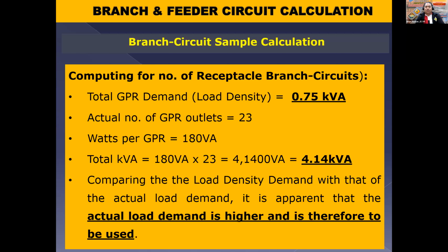Now, whichever is bigger, the load density or the actual load. In this case, mas malaki si actual load. So, which yung gamitin natin? Si 4.14 or the actual load, di ba? So talaga yung mas malaki. So during this stage, mag-validate na tayo, no? I-adjust na natin yung design natin. Okay?